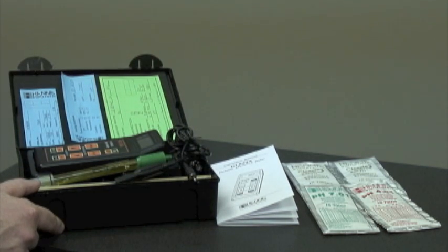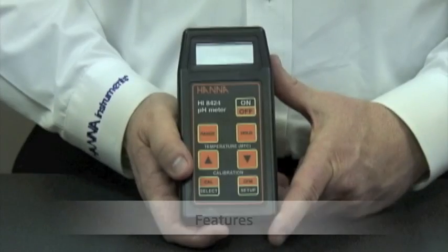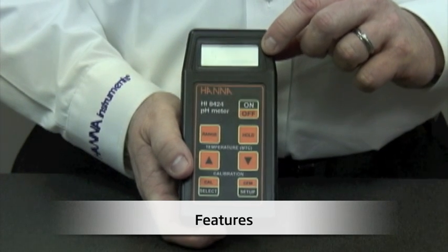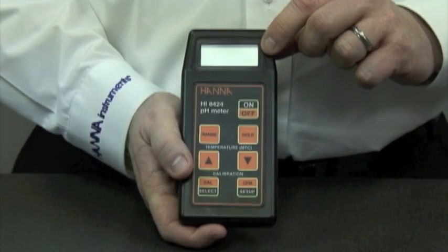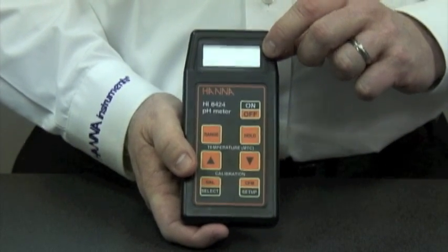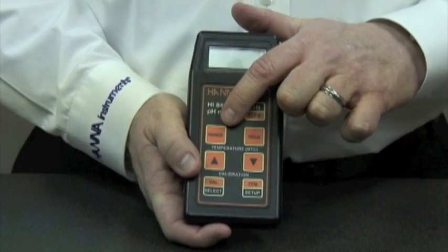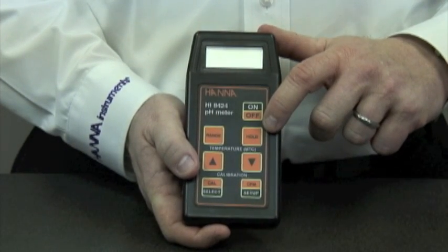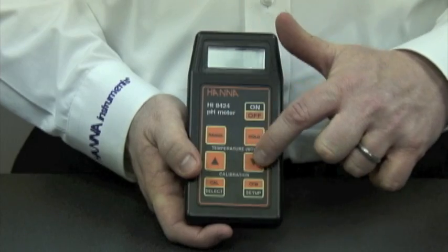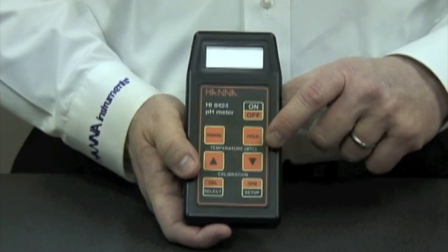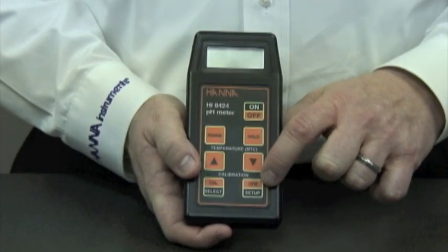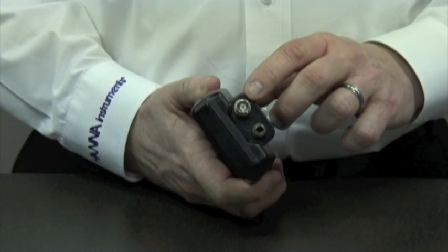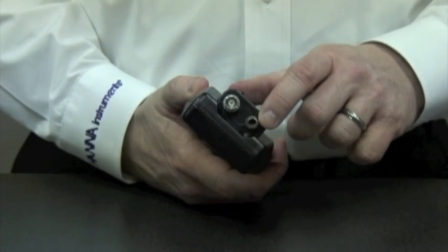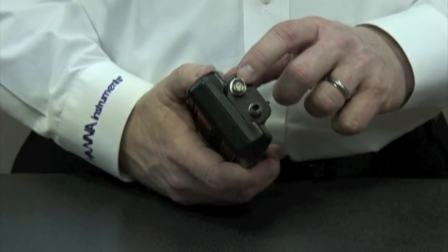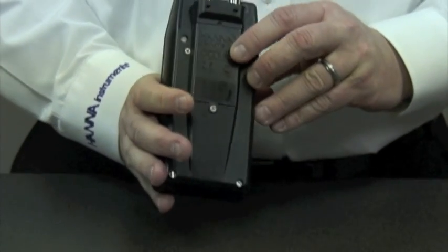Now I'd like to show you some features of the unit. Here we have the LCD display, which shows pH, millivolt, and temperature in either Celsius or Fahrenheit, the on-off button, the range button, the hold button that will hold the readings, temperature buttons for manual temperature compensation, calibration button, setup button. We have an RCA connector for the temperature probe, we have a BNC connector for the pH probe, and we have the battery compartment.